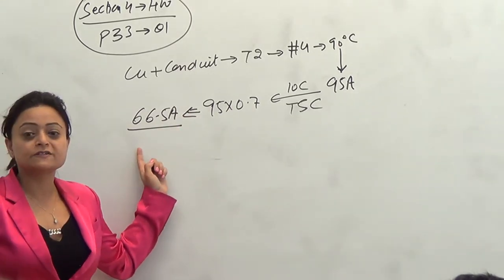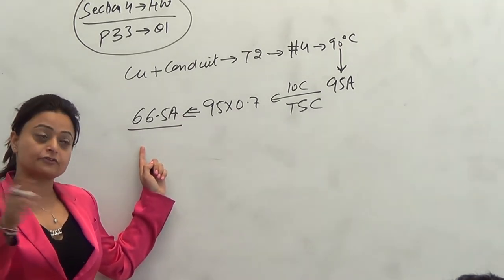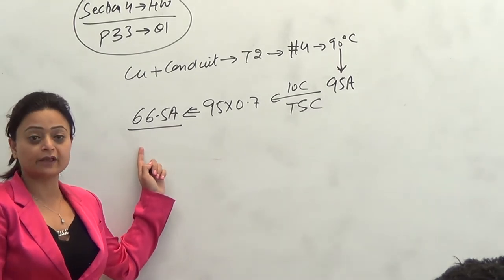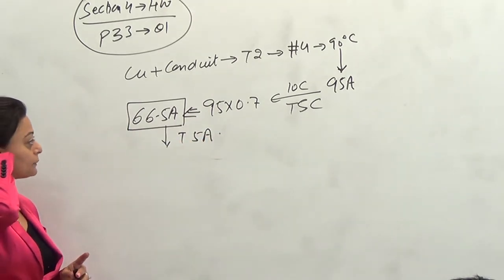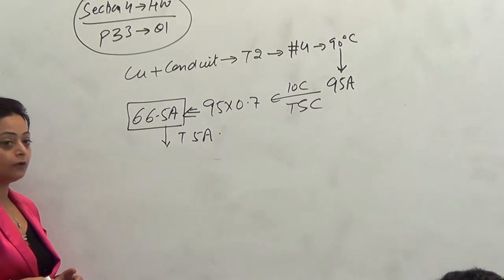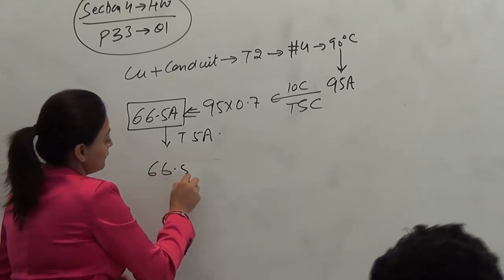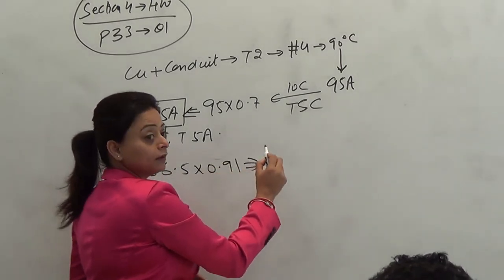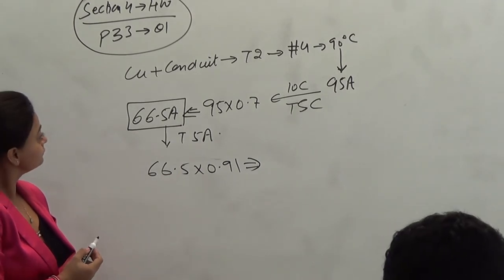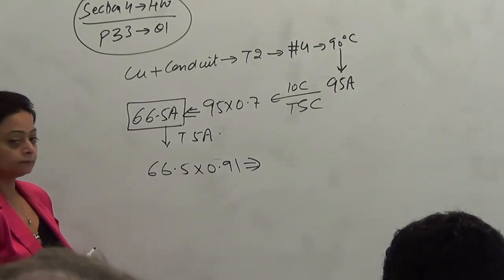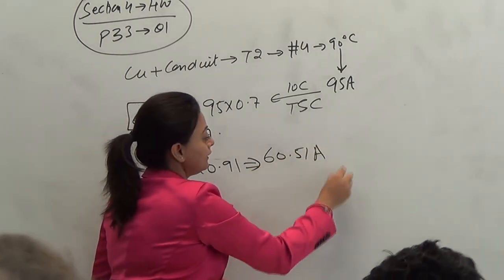I would stop right here if I was not told anything about ambient. Because it says that the ambient of this room is beyond 30. In this case, it's 40. I gotta go one step further, which is Table 5A. So, Table 5A, I'd like each one of you to go there. Look for 90 column and 40 row. It's 0.91. So, 66.5 times 0.91. What do you get? 60.51 will be my final answer.